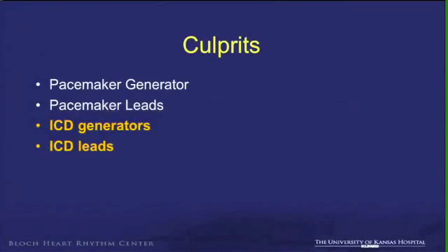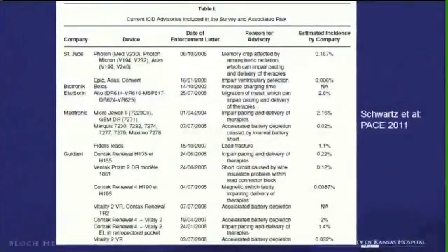So there are pacemaker generators, pacemaker leads, ICD generators, ICD leads. The pacemaker generators and leads have not been as common in the last 10 years. ICD generators and ICD leads have had many issues. So in the interest of time, I won't go into details of all the recalls. I'll go over a couple, 3 common ones which we're encountering in today's world, and go over the management of the same. So this is the list of all the ICD advisories.